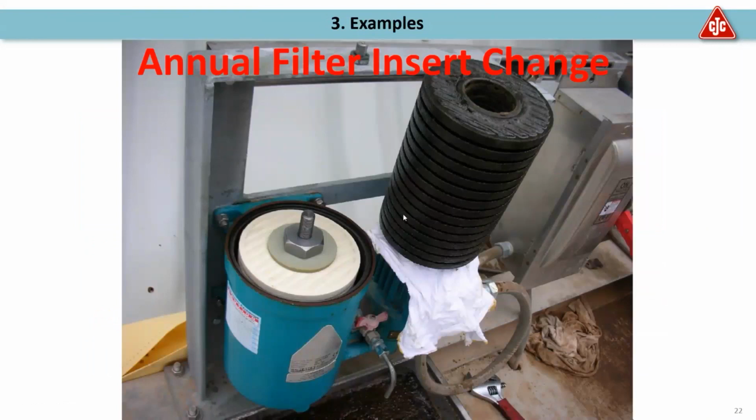Our filter units are designed so that you only have to do an annual filter insert change. This picture here shows a typical used filter insert placed next to a fresh one. And this one actually had also absorbed quite a bit of water in the cellulose here.